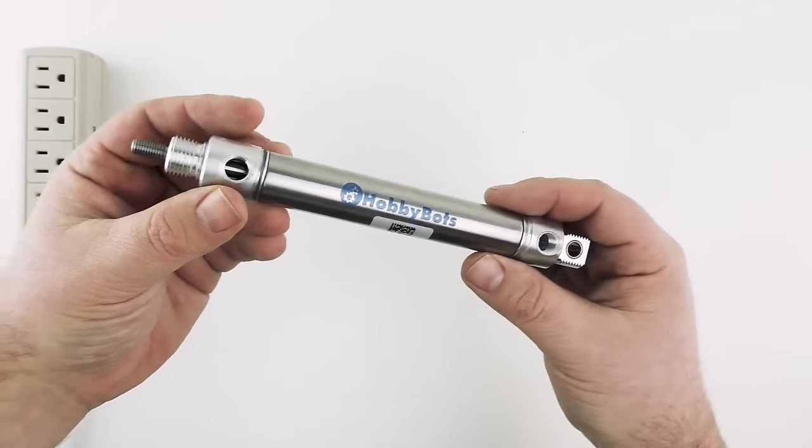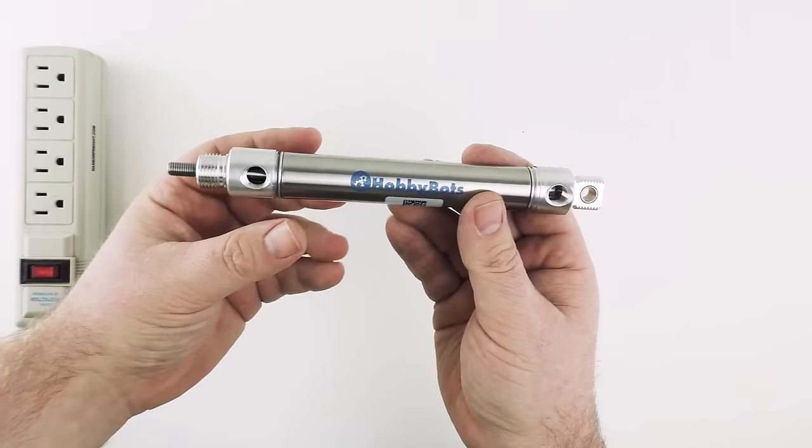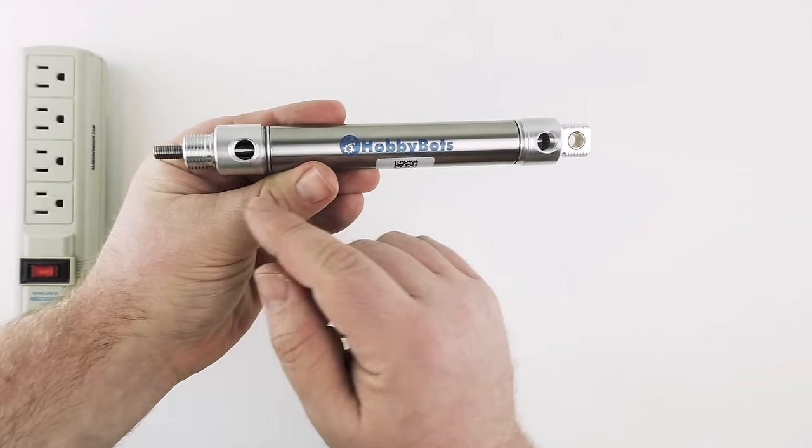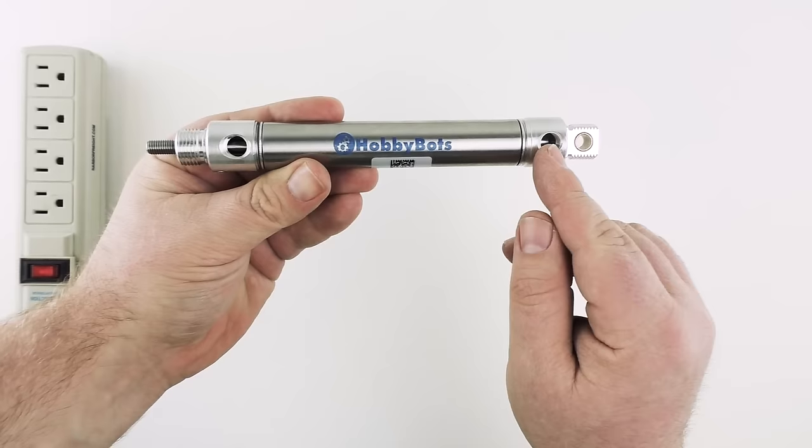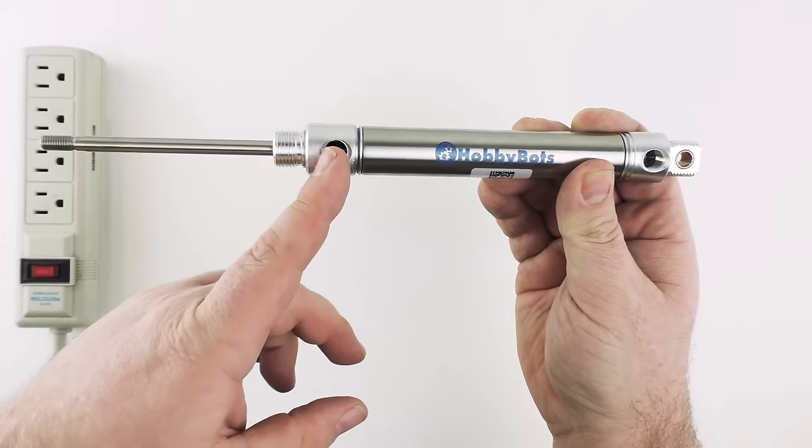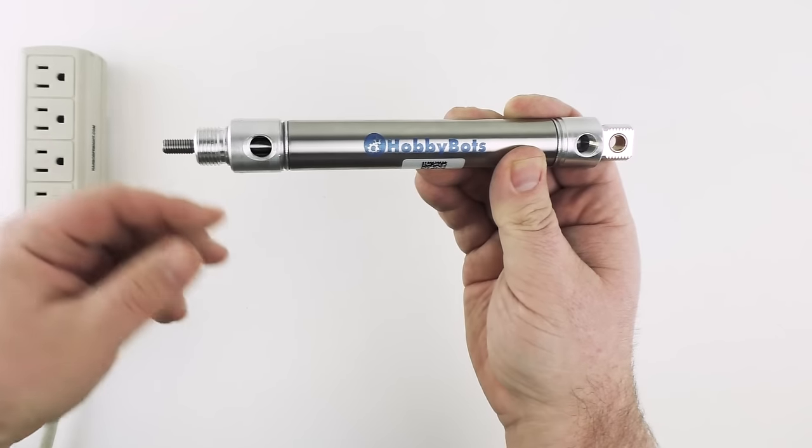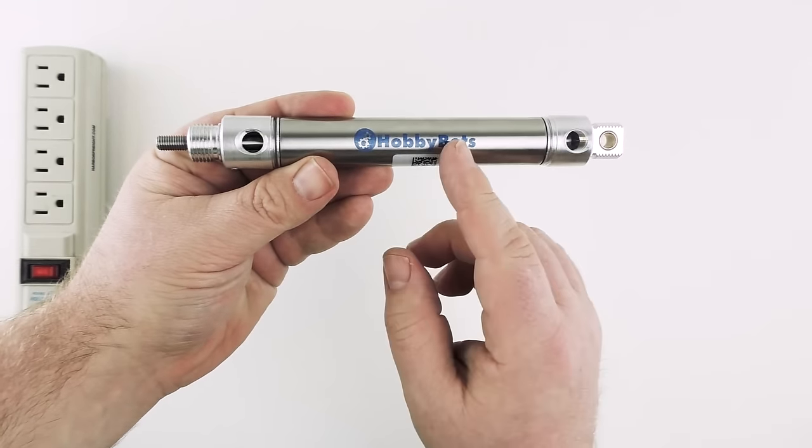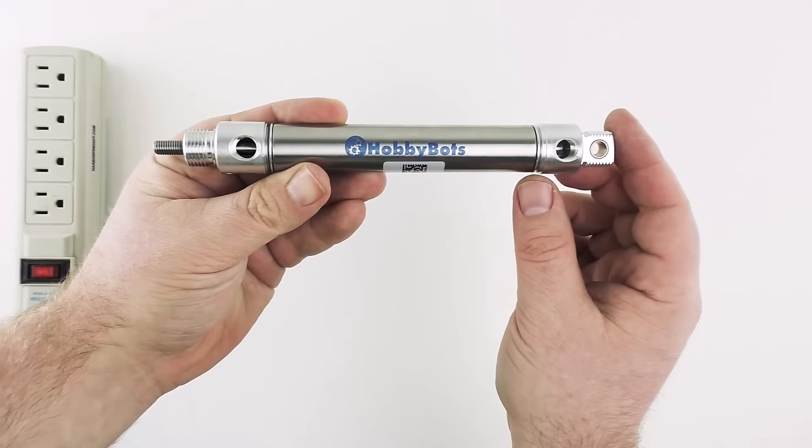The most common type of cylinder you're going to encounter is called a double acting cylinder and that's what this is here. You can see there are two air ports on this cylinder. One is for air to come in and push the cylinder rod out. When air comes into the other port it's going to pull the cylinder back in. So double acting meaning that it uses the power of air both to extend and retract the cylinder.